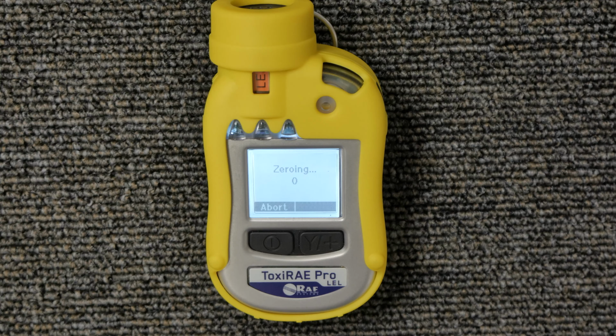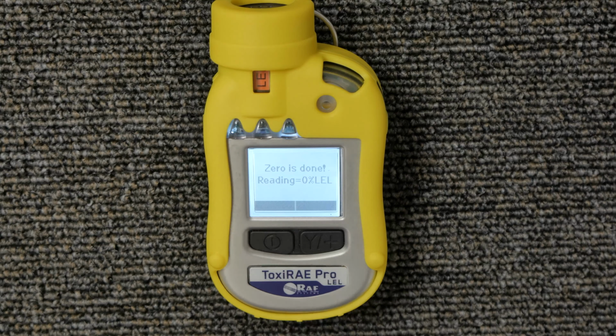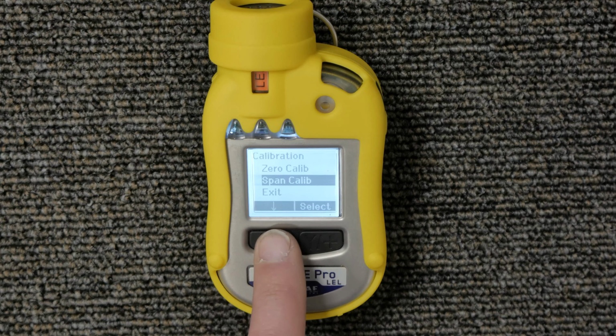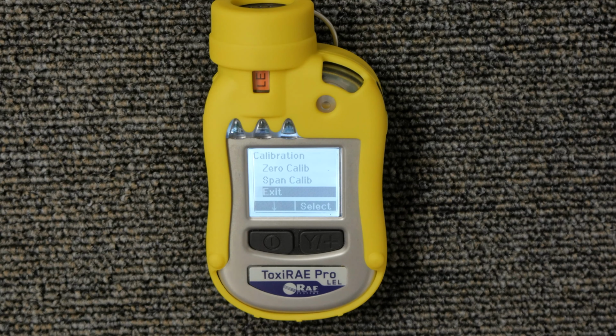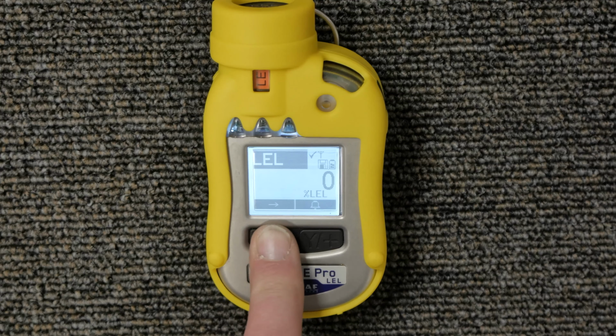And then once the calibration is complete, it will give you the 0 calibration reading of the 0% LEL. And then to exit out of the calibration menu, hit the power button to scroll down to the word exit, then hit the Y plus to select, and then you're back in live reading mode and your unit is ready to be used.